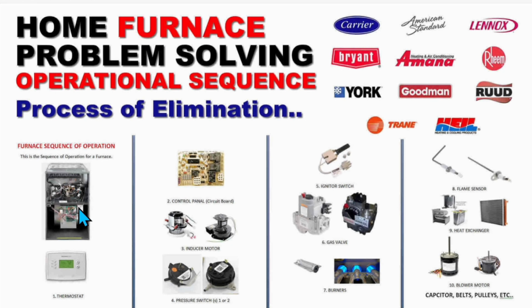Find your manual. You want to find your diagnostic chart so you'll know how things are laid out and how to find whatever component you're looking for. You also are going to want to know the electrical readings and requirements for each of these components in case you want to test them yourself. With that said, we have a call for heat, number 1, because we're at 59 degrees. The thermostat is hardwired to your control panel. There's going to be a slight delay, but number 2, the control panel takes the call for heat. Number 2, the control panel at that point tells the inducer motor.